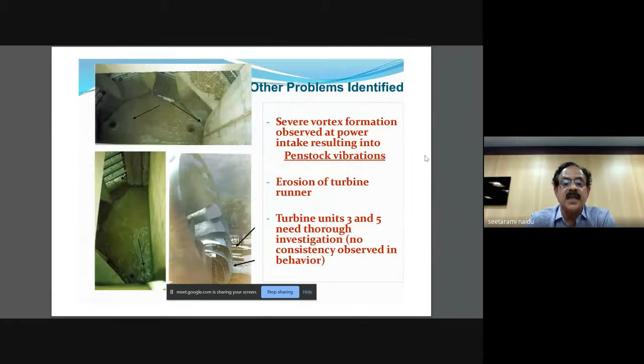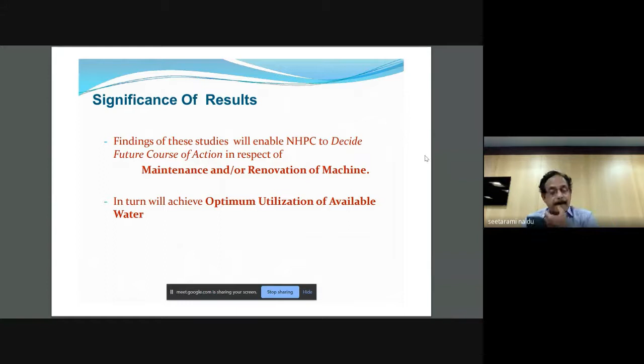Findings of these tests have enabled NHPC to decide on a new runner, and they have done so. They have given the order to Voith, a German company, and one turbine was tested in their own lab, witnessed by NHPC people. We have witnessed the acceptance test. It was acceptable. The claimed efficiency of 94% was possible, and much higher than that was realized. And now, based on one test turbine, they are supplying 6 turbines.